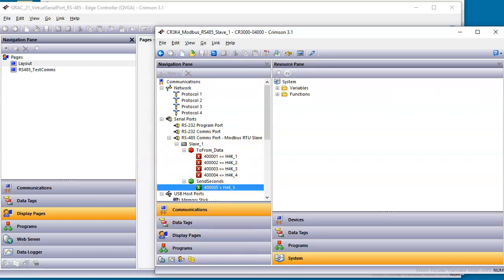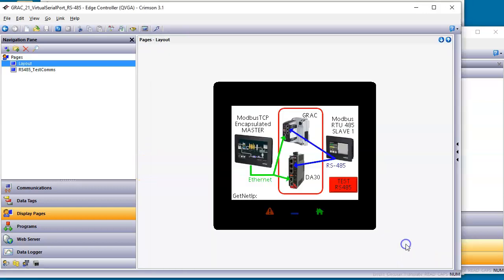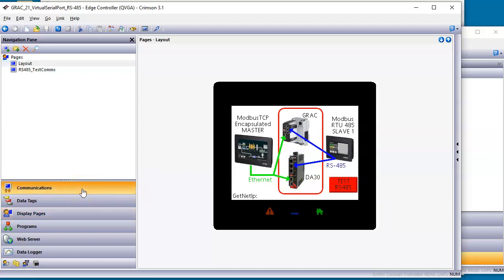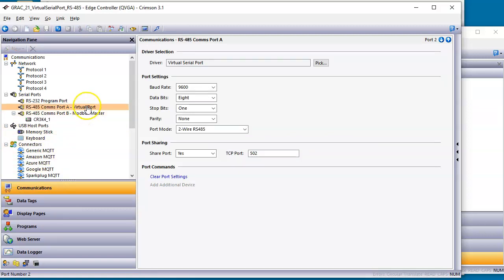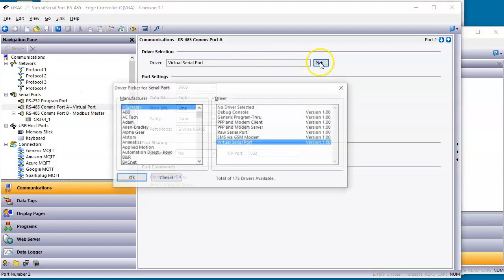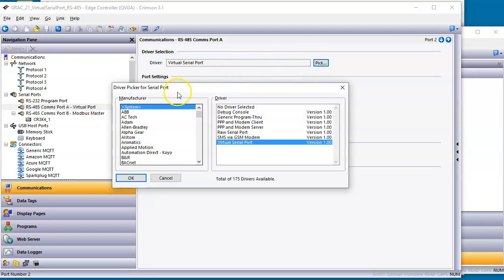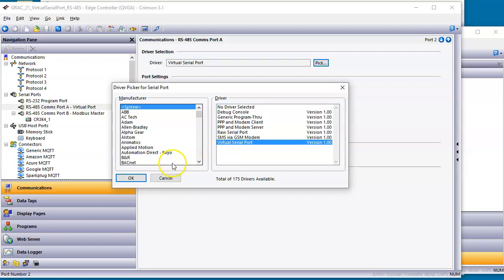And then my center one, which is the GRAC unit in this case. This is the layout. If I go to communications on it, you can see what I'm doing here that's interesting is I'm using the first 485 port. I've set it up as a virtual port. How I did that is over here where you pick drivers, right under the main system driver, there's a virtual serial port driver I'm using. This feature is supported in the DA30 and in this case, I'm using the GRAC for this.